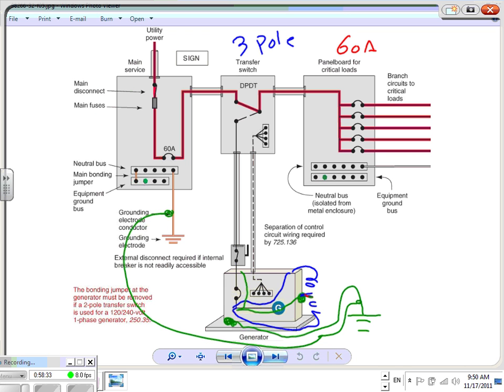Then I need to change this one into a 2-pole circuit breaker, and I'll take my neutral. I'm going to follow my neutral right in here. Where's my neutral bus? Right in here. I'm not switching the neutral, and my neutral follows all the way to the neutral bus, right in here. If I do it this way and I don't switch the neutral, these are all neutral. If I do it this way and don't switch the neutral, this is called a non-separately derived system. If I switch the neutral, then it becomes a separately derived system.